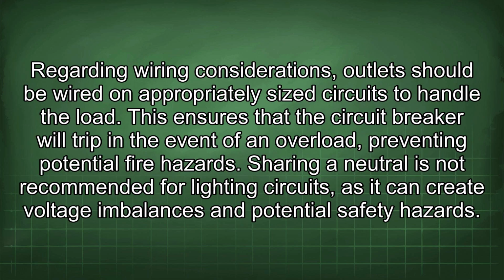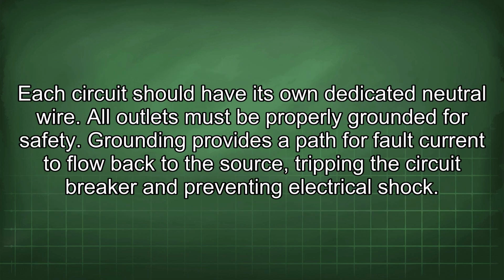Regarding wiring considerations, outlets should be wired on appropriately sized circuits to handle the load. This ensures that the circuit breaker will trip in the event of an overload, preventing potential fire hazards. Sharing a neutral is not recommended for lighting circuits, as it can create voltage imbalances and potential safety hazards. Each circuit should have its own dedicated neutral wire. All outlets must be properly grounded for safety.